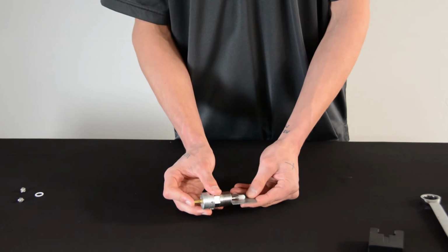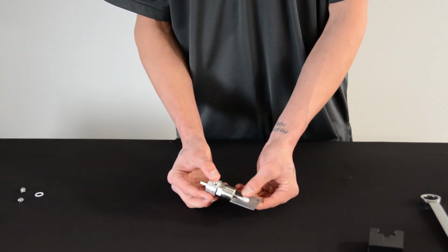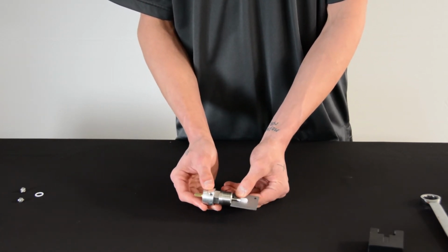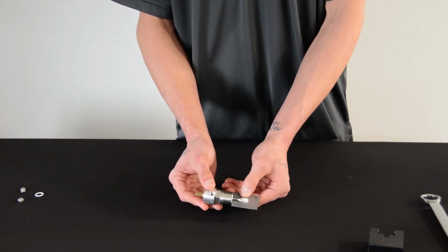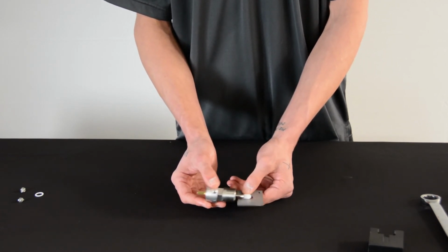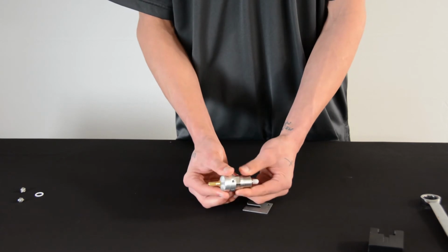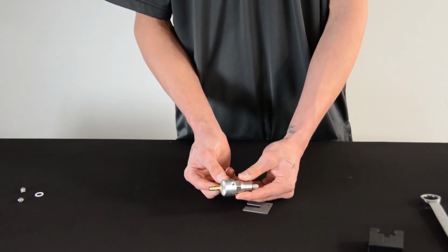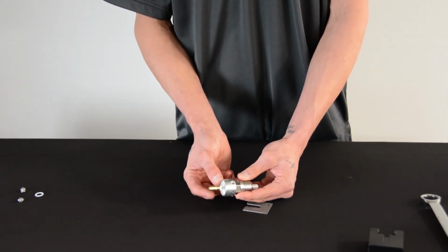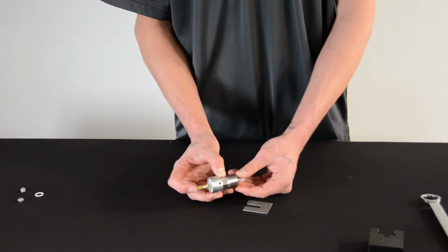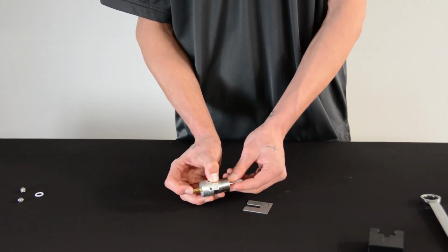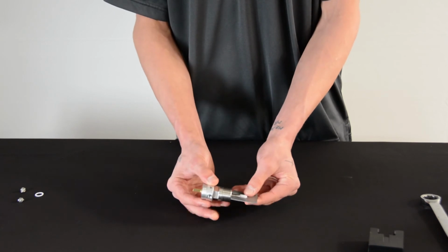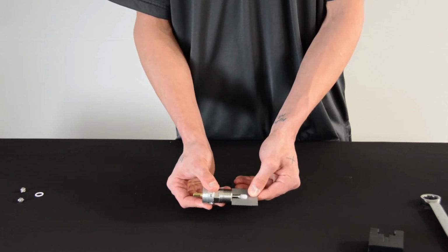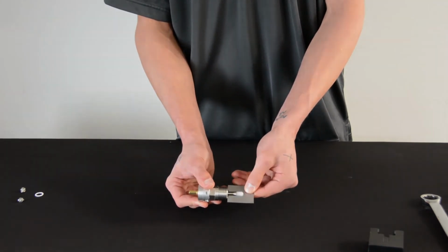You want to push your piston through the Poppet valve and make sure it's fully seated up against the calibration gauge. And then you're going to go through by pushing your shaft back through and tightening your piston retaining nut and locking nut indicator together. Once you have tightened them back together, you're going to push your shaft back through and double check with your calibration gauge to make sure it is fully seated up against the bottom of the calibration gauge.